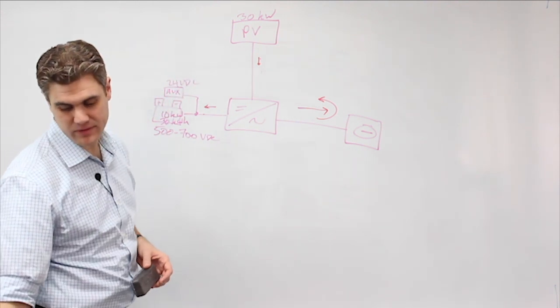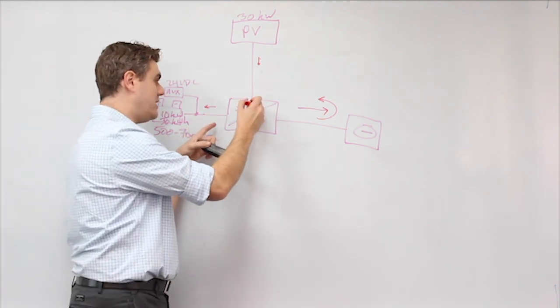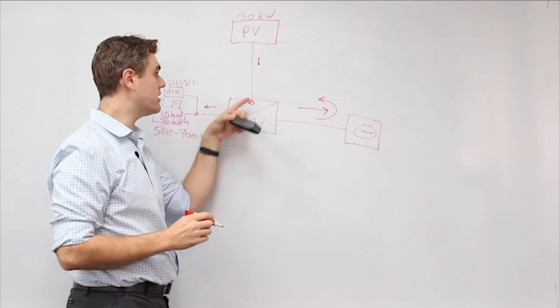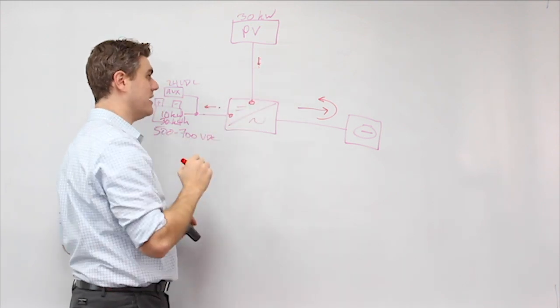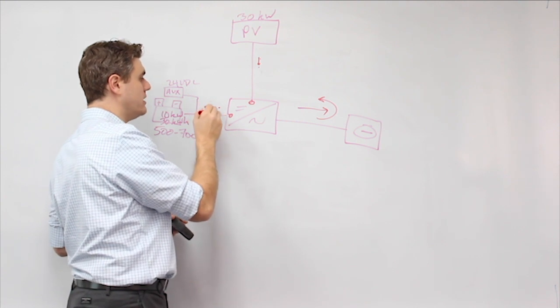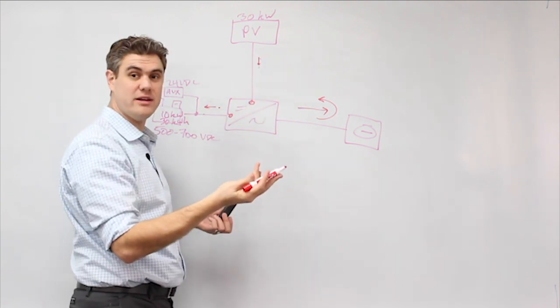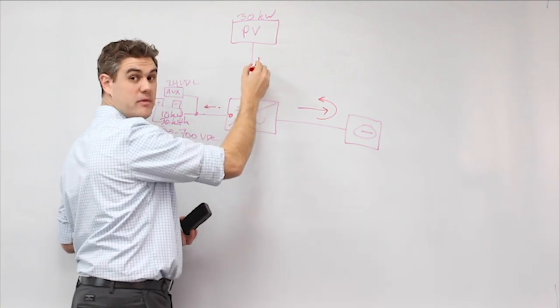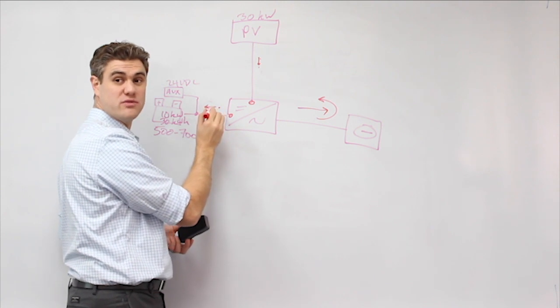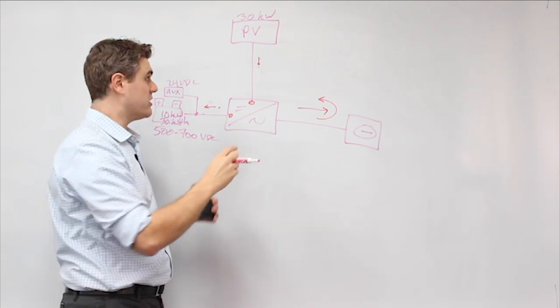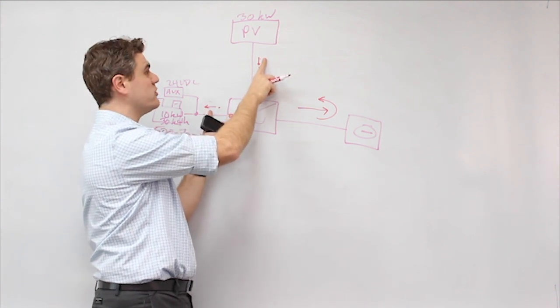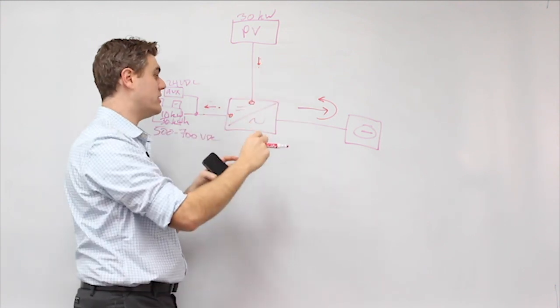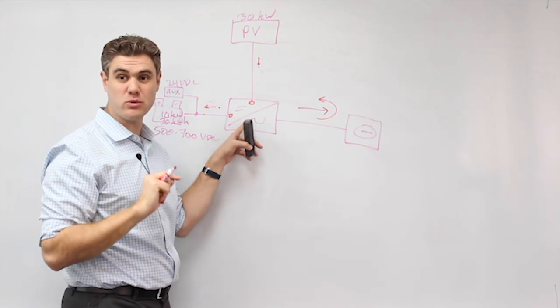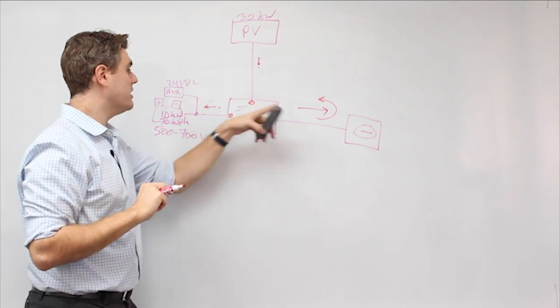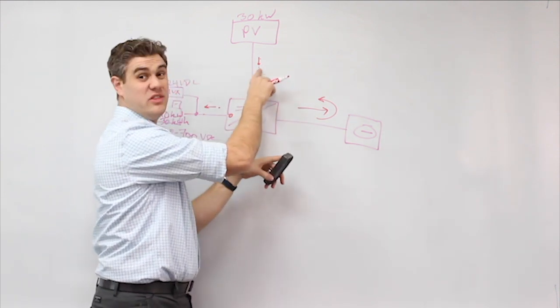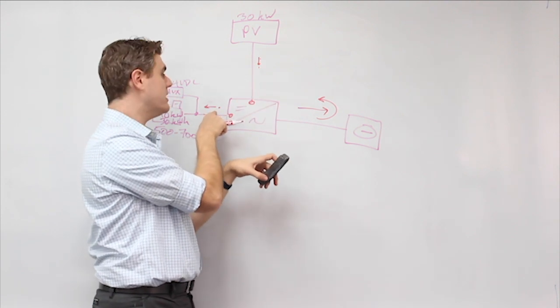Before that even happens, this inverter is sensing these two ports right here. And it can see the difference between this guy and this guy. So long as this arrow is smaller than this arrow, everything's fine. But the moment this arrow gets too small, this is going to flip, and this is going to start charging from the grid. And there is some safety factor here. It's not when these are exactly the same size, but when they're approaching the same size that the inverter does something really clever. It detects that this arrow is getting dangerously close to the size of this arrow. And what does it do?